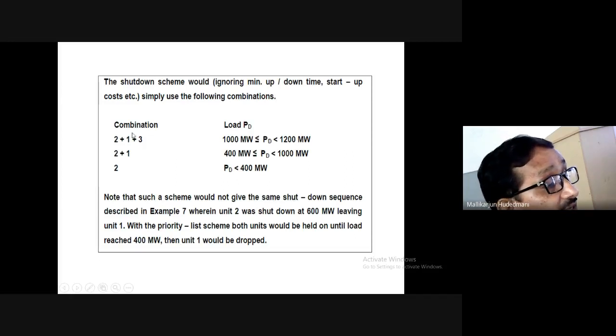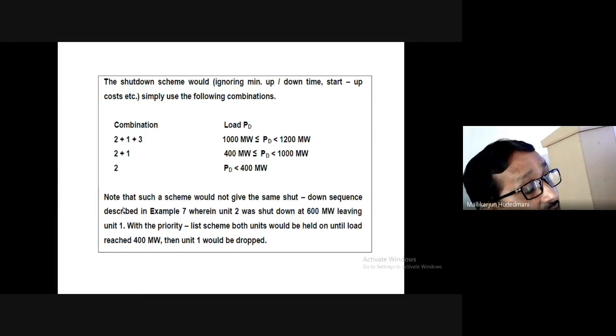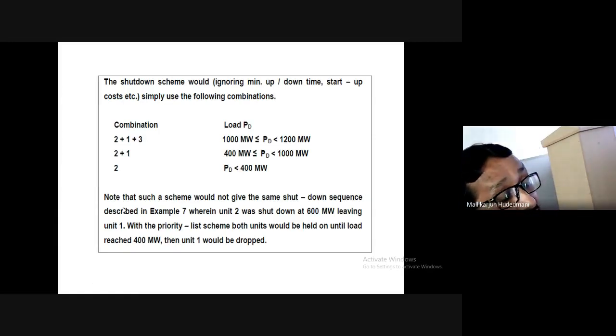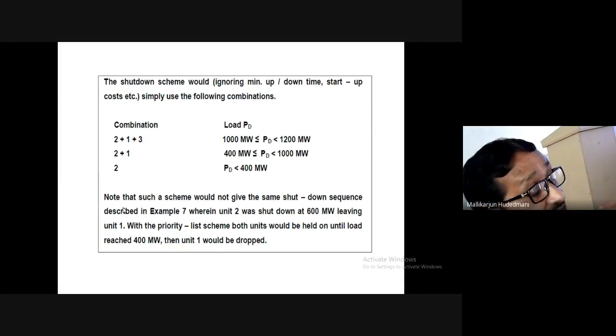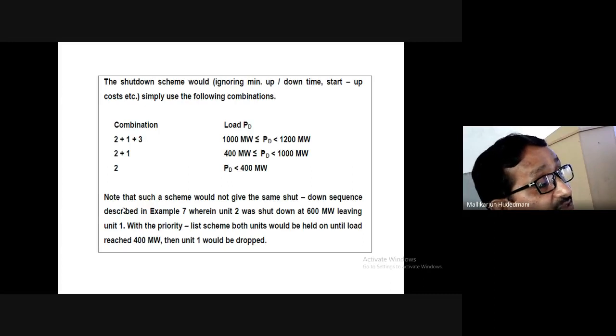Then if I want to do a shutdown, the load is decreasing. Remove 3 first. Remove 1 later. Remove 2 later. So withdrawal is in reverse, while startup follows the priority. Commitment in the order of priority, decommitment in the reverse order, because the very latest added machine is costlier. That has to be eliminated first; it is a rule of priority. This way, another example is cited for you.